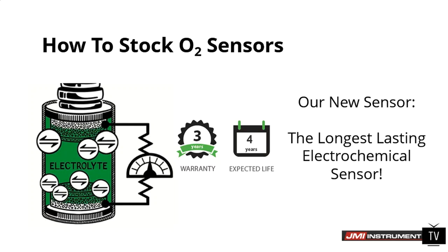Now, we launched these sensors in 2017. Prior to that, we were testing, and those sensors that we had on the shelf, we routinely check them to see if they're still alive or not, and we haven't been able to fail them since development of this new platform. So in the past, if you had a spare sensor on the shelf, you may have got 6 months, maybe less out of that spare sensor. Now you should be able to get the full life of your oxygen sensor, which in the world of oxygen sensing is a pretty big deal.